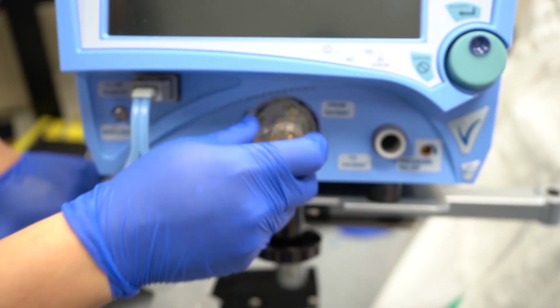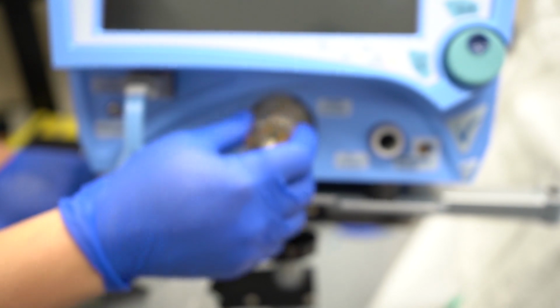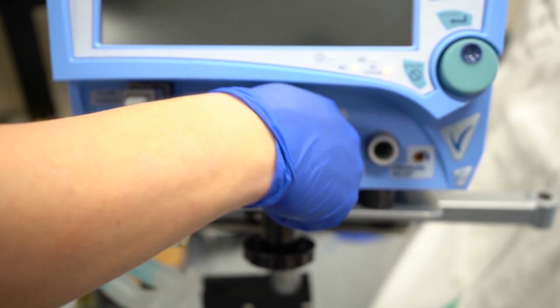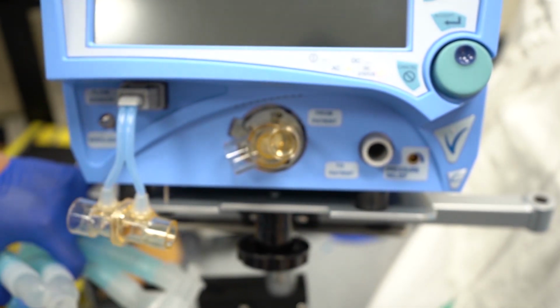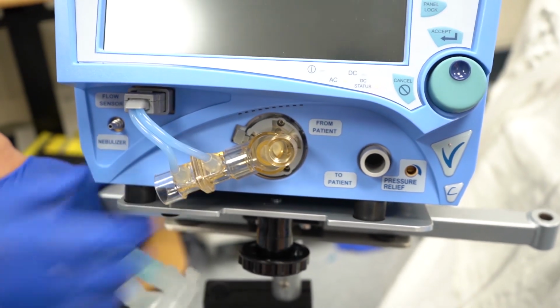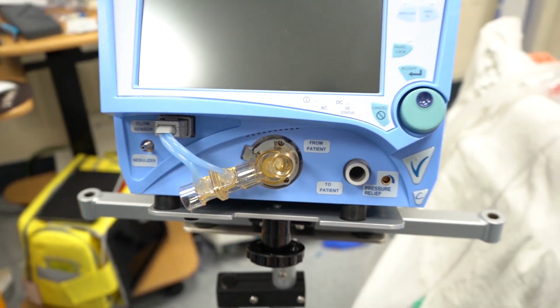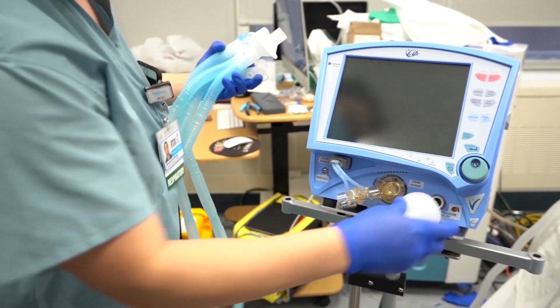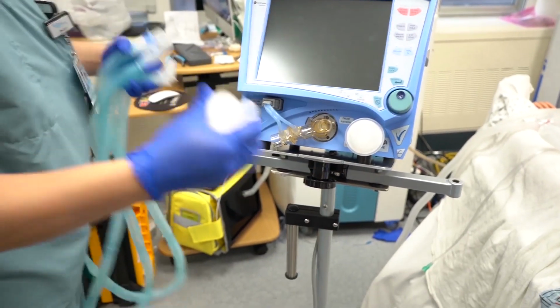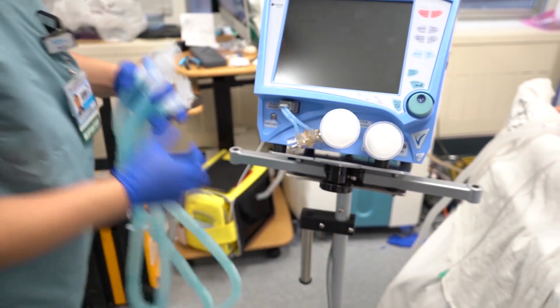To get the valve back on, it only fits one way. Press it in, twist until you hear a click. Reconnect your flow sensor. We're going to put two filters, one on the inspiratory, one on the expiratory, and then your standard non-heated disposable circuit.